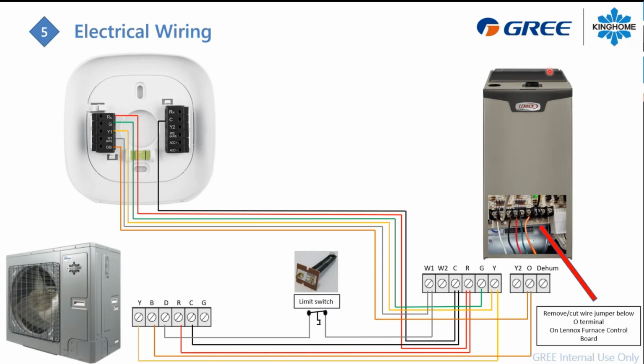So just during the defrost cycle, when it's done, the unit will go back into heating mode, and then you will heat the house with the heat pump again. So the D terminal here just connects to W1 to prevent the cold draft into the house, and that's it. If in your region you don't use the heat pump at very low temperature, the defrost will not take too much time, so maybe you don't have to connect it. But from a Quebec perspective, or when you're using an electric air handler, maybe at some point it's good to have this W1 connected with the defrost.